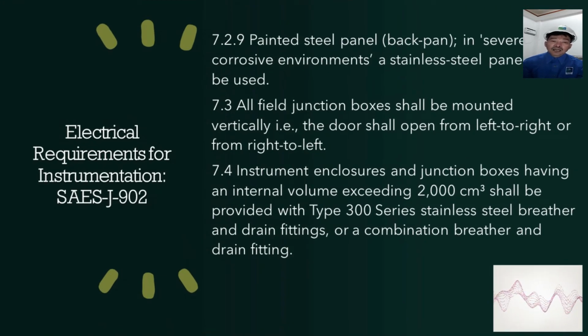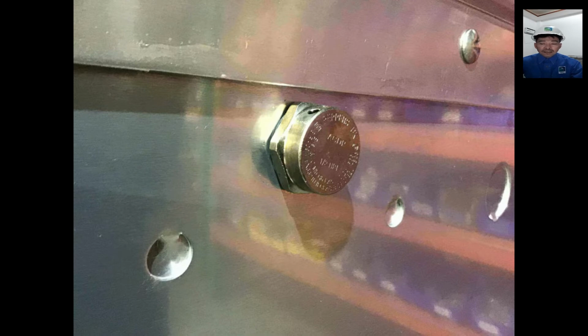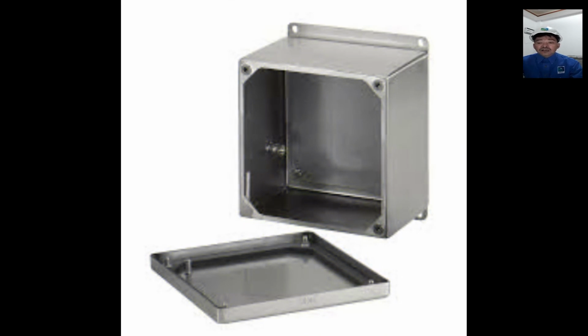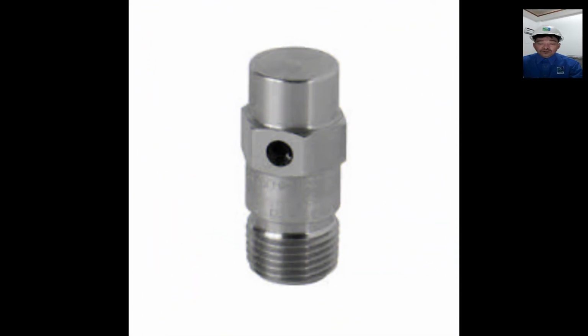Instrument enclosures and junction boxes having an internal volume exceeding 2,000 cubic centimeters shall be provided with Type 300 series stainless steel breather and drain fittings or a combination breather and drain fitting. So this is very important. During the installation, you're going to find junction boxes which do not require a breather or drain, because the requirement applies to volumes exceeding 2,000 cubic centimeters. These are the junction boxes which require a breather and drain, or a combination of breather and drain fittings. So please take note of that.